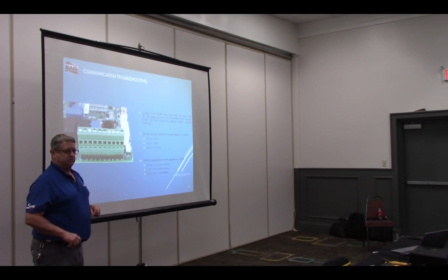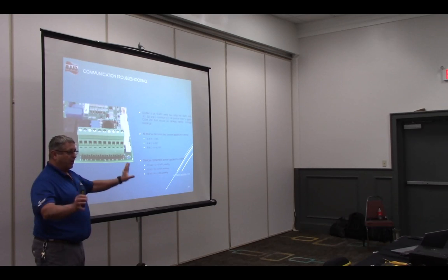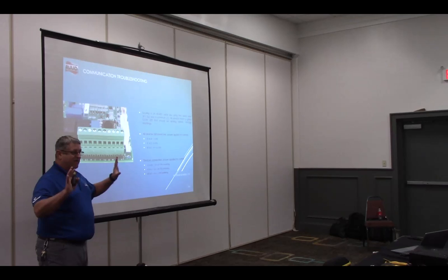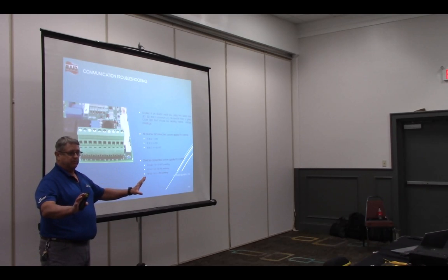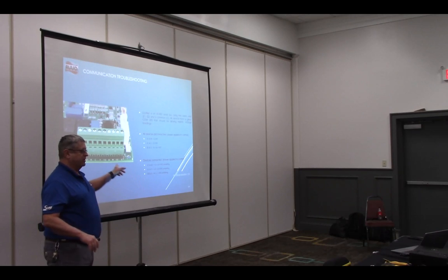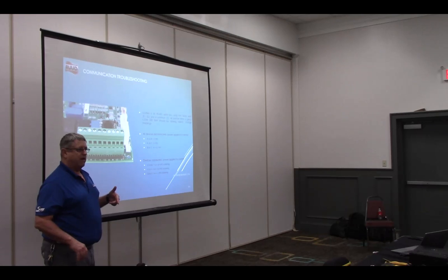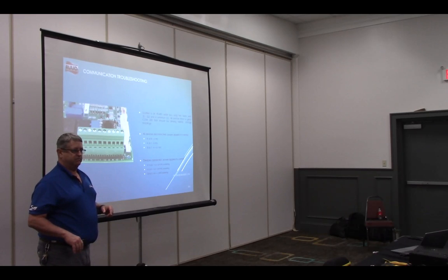So what's wrong? We have an outdoor communication error. We know our boards are good, right? So we have a wiring problem. But where is it? Inside somewhere. Where? Thermostat. Or could it be between the furnace and the outdoor? How do we check that? Now how do we check it? How do we know? I'll tell you.